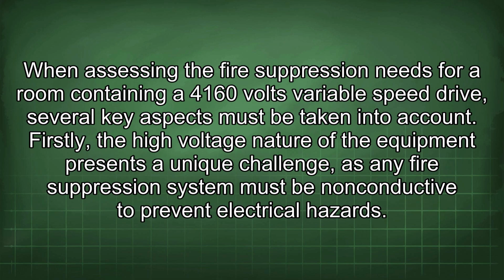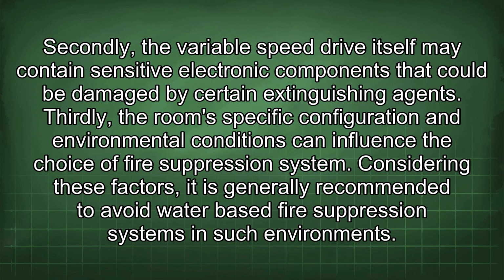When assessing the fire suppression needs for a room containing a 4160 volts variable speed drive, several key aspects must be taken into account. Firstly, the high voltage nature of the equipment presents a unique challenge, as any fire suppression system must be non-conductive to prevent electrical hazards. Secondly, the variable speed drive itself may contain sensitive electronic components that could be damaged by certain extinguishing agents. Thirdly, the room's specific configuration and environmental conditions can influence the choice of fire suppression system.